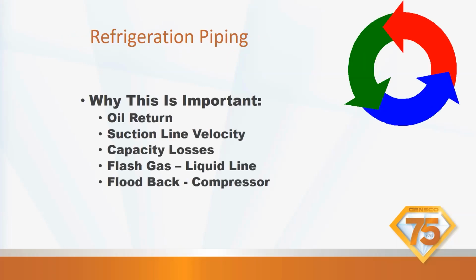Why is refrigerant piping so important? Oil return. If we have suction line velocity issues, if our line set is too big or too small, we're going to have capacity losses. We're not going to get the oil back to the compressor where it needs to be. It's going to stay out in the system. It's going to stay in the line set and in the indoor coil. We're going to have major issues with killing compressors.